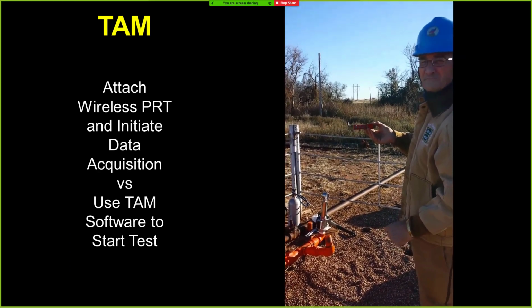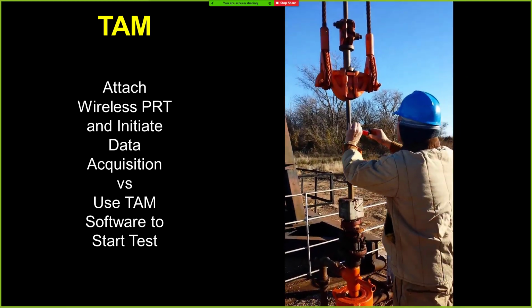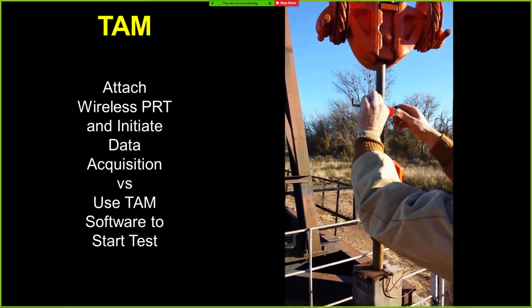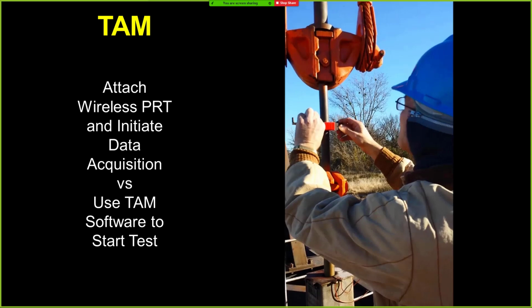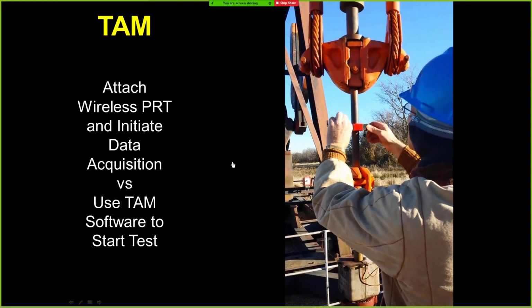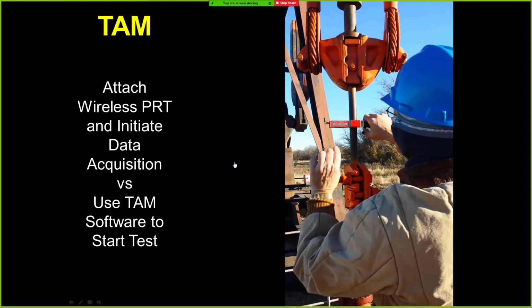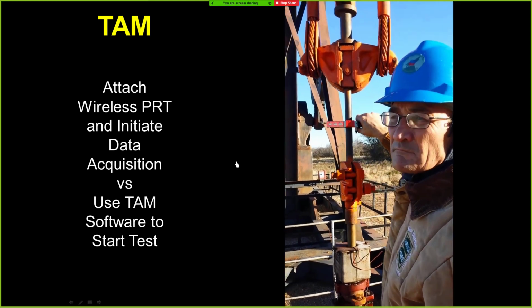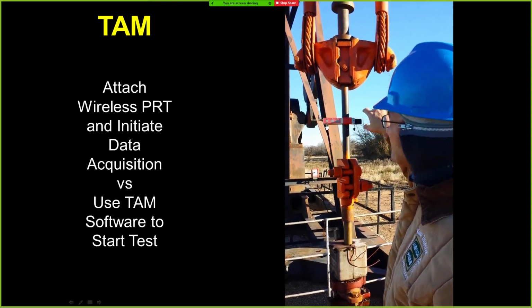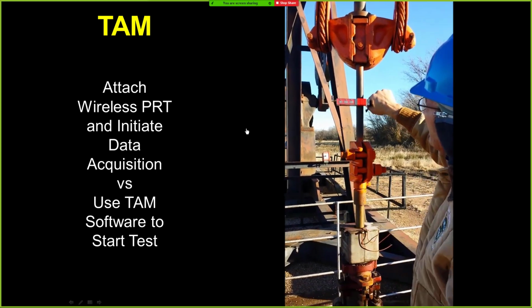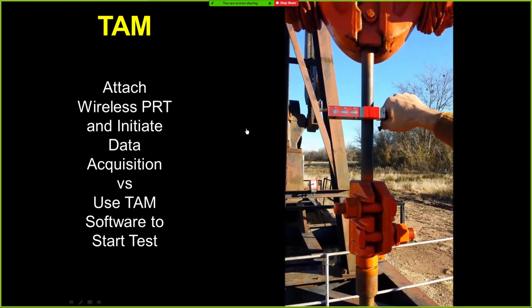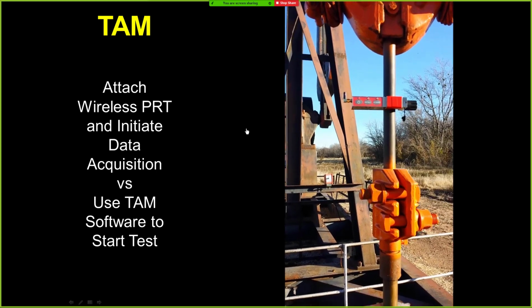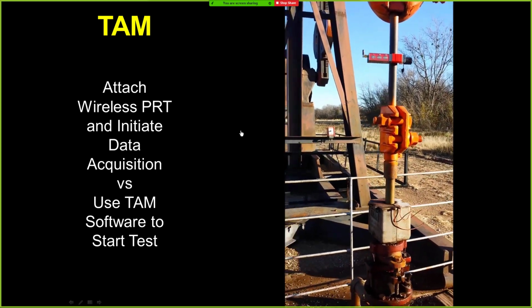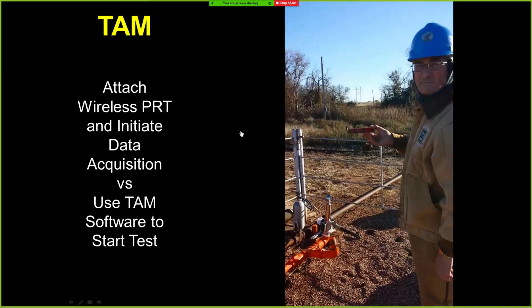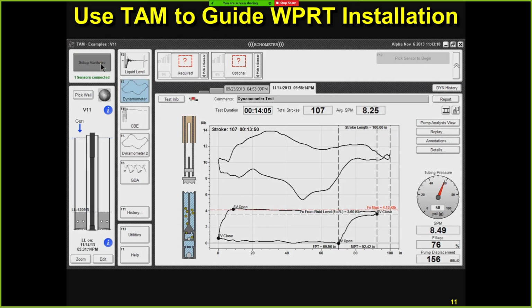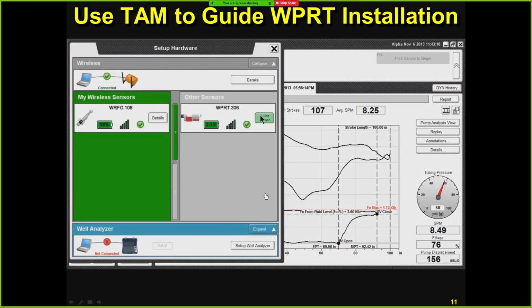Now this is us out at the well, attaching the wireless PRT to the well. And you can hear the wind noise, and you can hear Ken. And I'm saying, hey, Ken, look at the screen. He says, no, I don't have to look at the screen, because if I just tighten the handle, I can see that it's properly tightened without looking at the screen. So that's one of the advantages of the wireless equipment, is that you can see that it's tightened without walking back and forth between the computer and the well. So it's much quicker. Now here's looking at the screen in TAM.